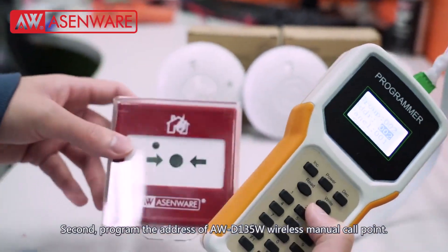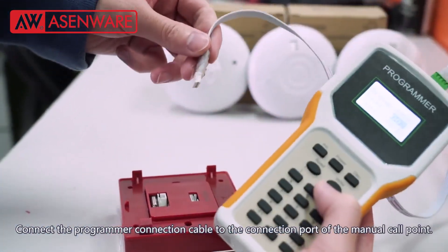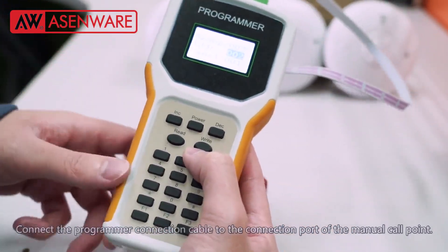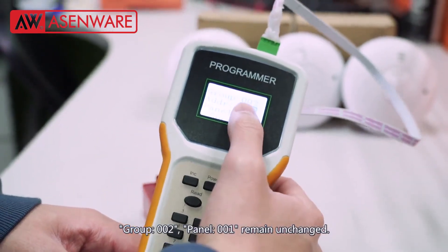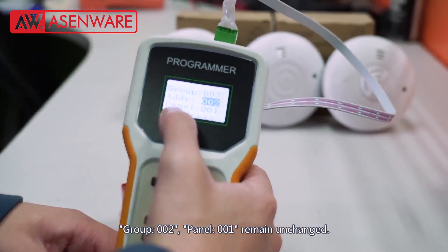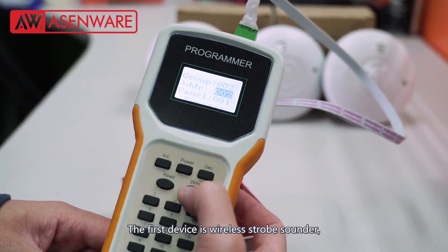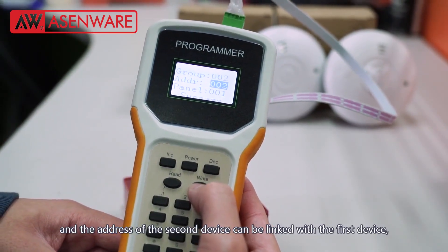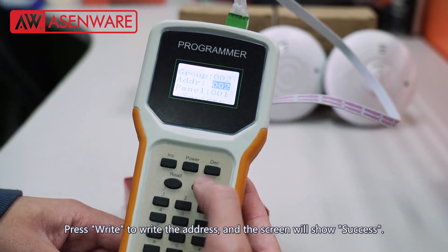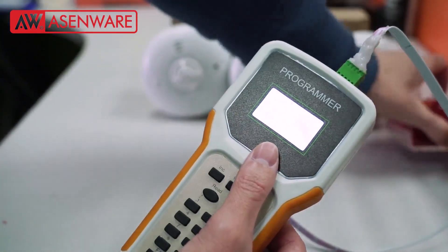Second, program the address of the AWD135W wireless manual call point. Connect the programmer connection cable to the connection port of the manual call point. Group 002, Panel 001 remains unchanged. The first device is the wireless strobe sounder, and the address of the second device can be linked with the first device, so the address of the manual call point can still choose address 002. Press Write to write the address and the screen will show success. Then pull out the programmer connection cable.